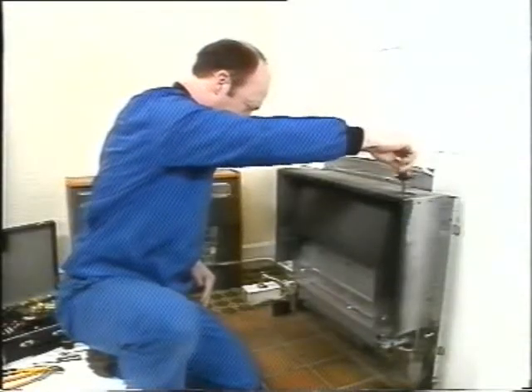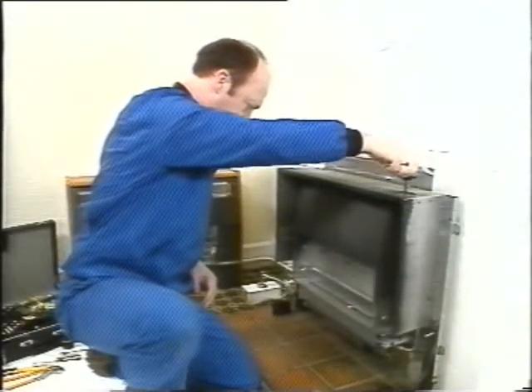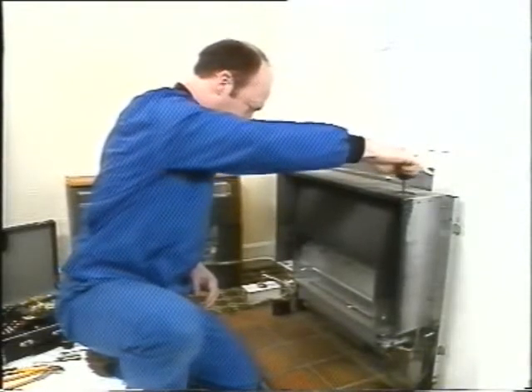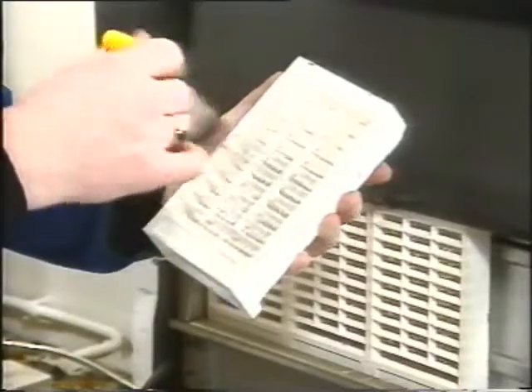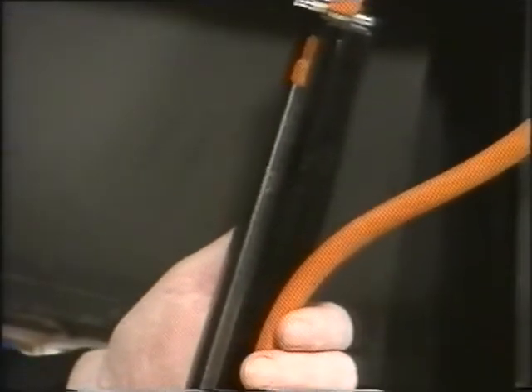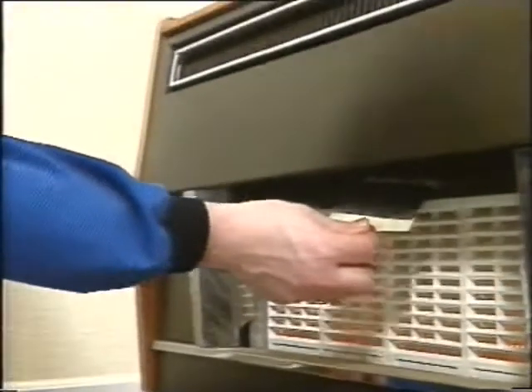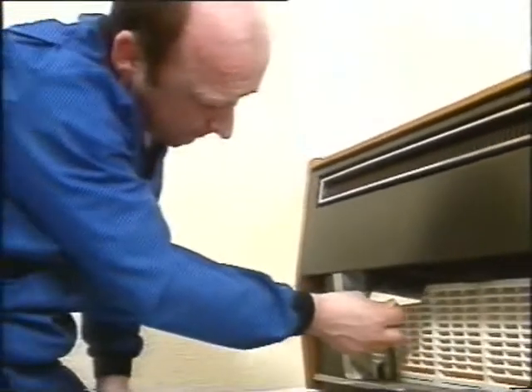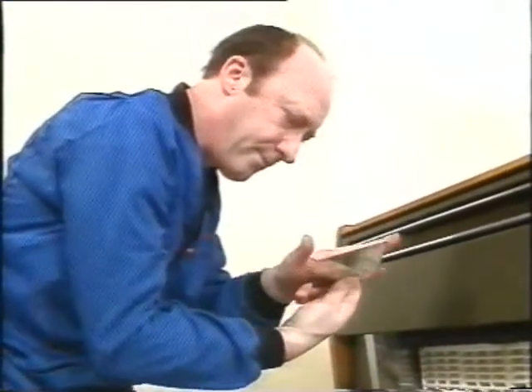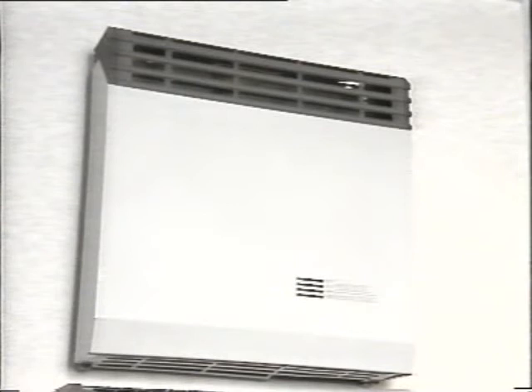The next check is on the ignition system and, if there is one, the flame safety device. Clean the radiants, put them back, then check the burner pressure. If everything's okay, you can now put the case back on, test the fire for spillage, and clear up the work area. These guidelines apply to all types of heaters.